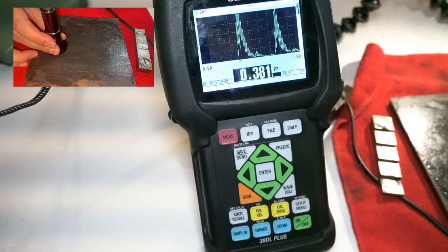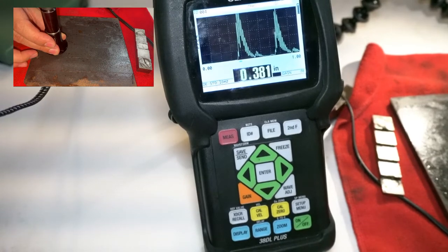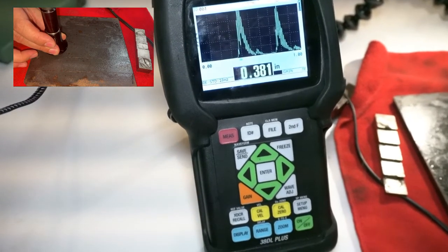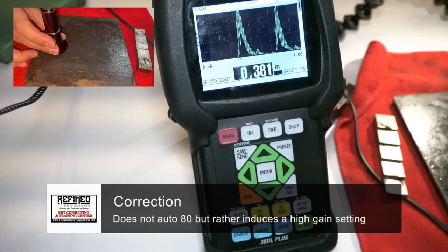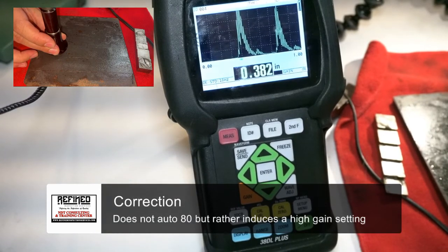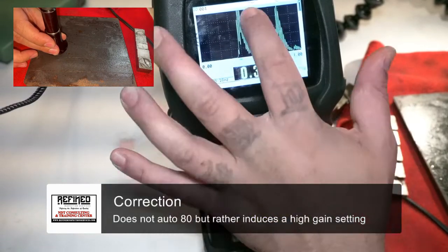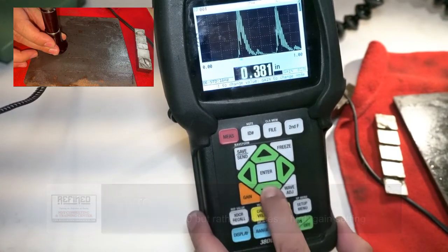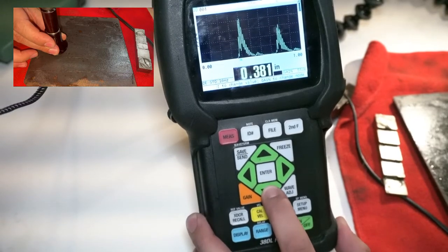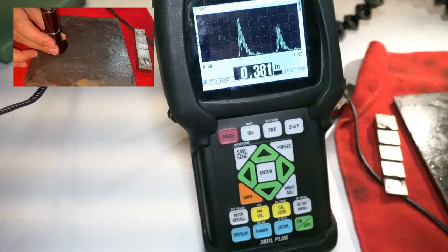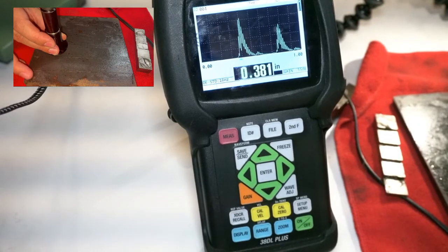So the 38 actually has a function where it auto 80s all of the signals. What I mean is it brings all the peaks up extremely high. And what we want to do is actually bring that peak down to about 80%. So we're gonna set a reference level to about 80% so that we can actually see the signals a little better here.